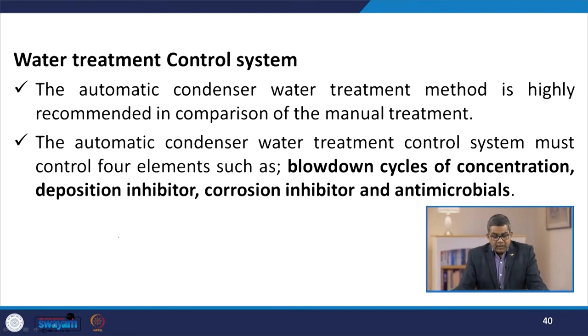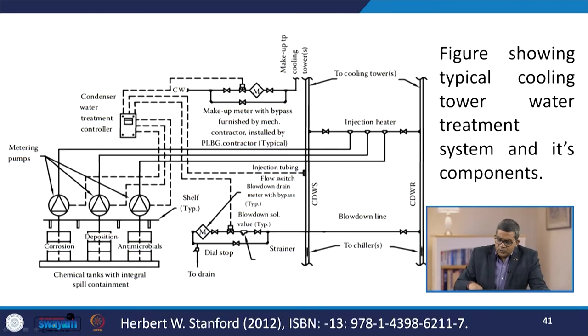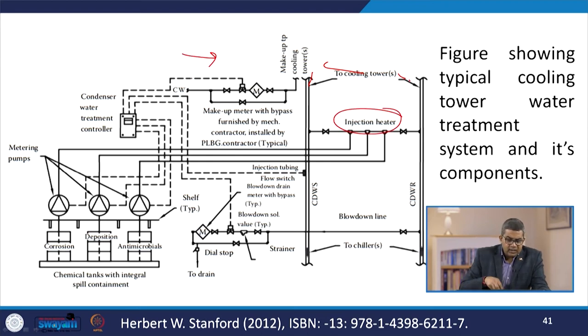Water treatment is a very crucial aspect. Let us discuss the water treatment control system. The automatic condenser water treatment method is highly recommended in comparison to manual treatment. The automatic condenser water treatment control system must control four elements: blowdown cycle of concentration, deposition inhibitors, corrosion inhibitors, and antimicrobials. A typical cooling tower water treatment system and its components include cooling tower lines and injection feeders among various components enlisted for the treatment of cooling water.